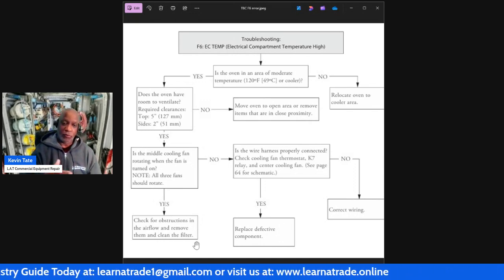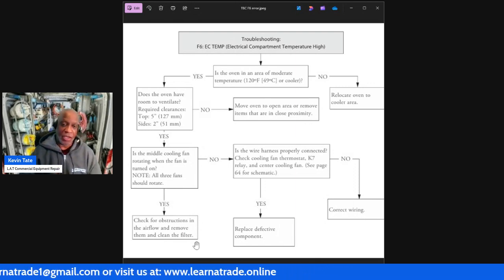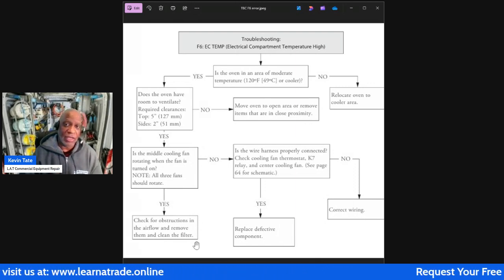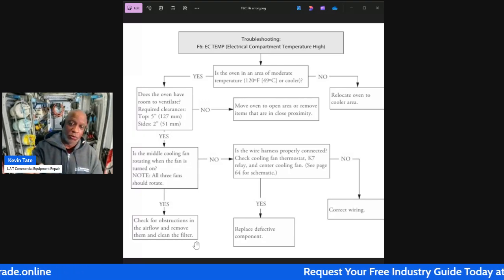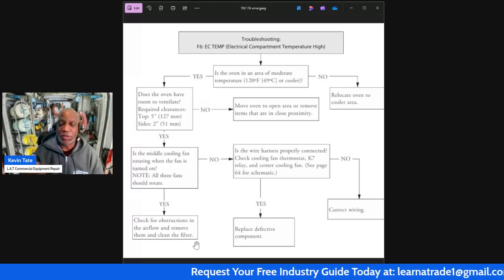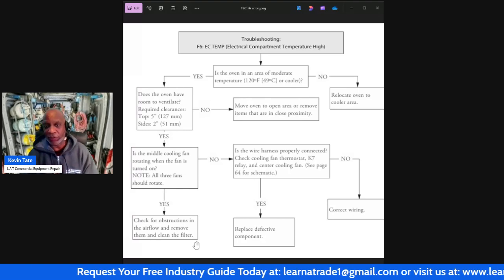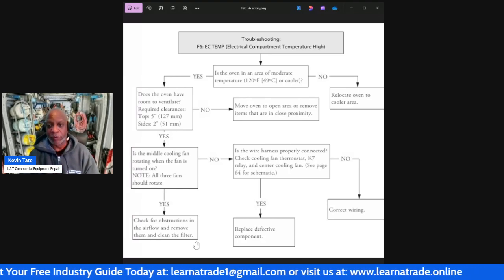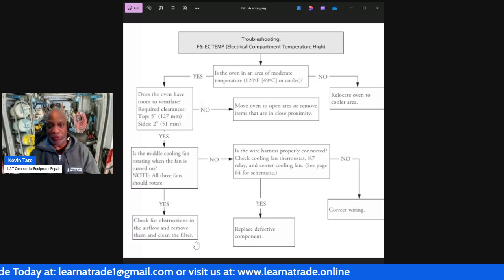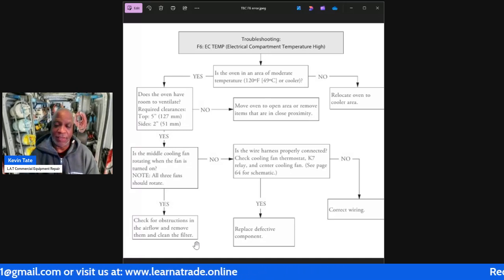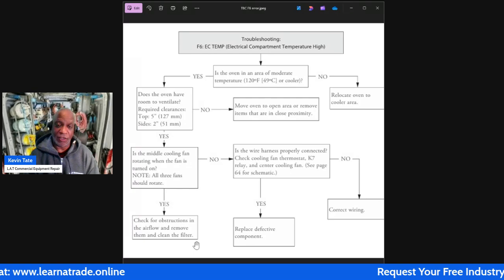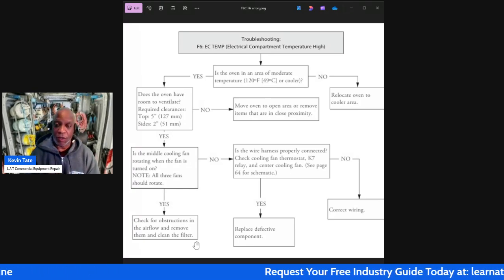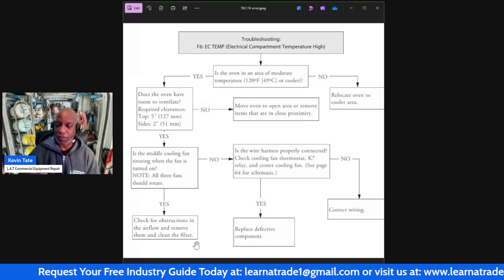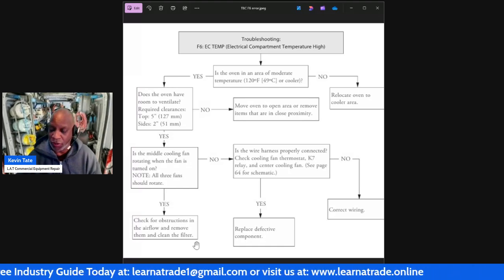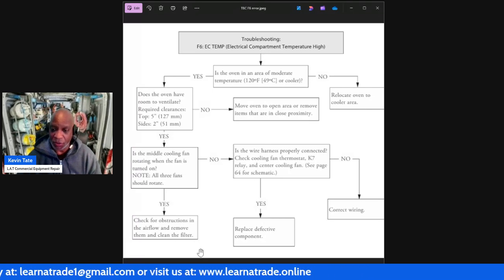When I first came on, I told you, when I see an F6, I go right to the filter. On the flow chart, it leaves that filter for last, but out in the field, you usually try the simplest things first. I go right to the filter because 9 times out of 10 it's not clean, it's clogged, and it's blocking the airflow. I suggest checking that first to cut down time so you're not held up on a job you could already be done with.